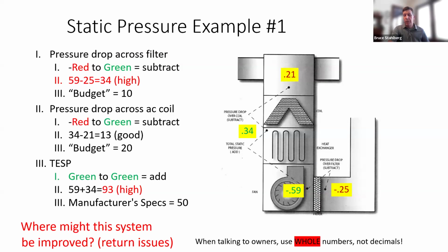Here's an example. I'm going to try to do this. So notice my measurements are -0.25, -0.59, 0.34, and 0.21. The first 2, we subtract those because it's a pressure drop. And coming in at 34, that's a little bit high for a filter. Doing the same thing across the coil, we got 13, and that's pretty good for a rough budget of 20. And then the total static pressure, which is TESP, we add those 2 numbers, and that's 93. So we ask, well, with these numbers, where might we improve this system?